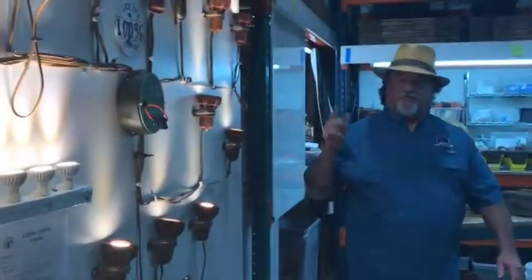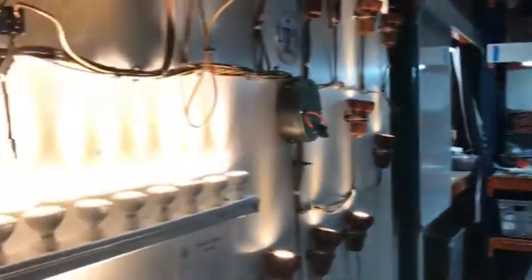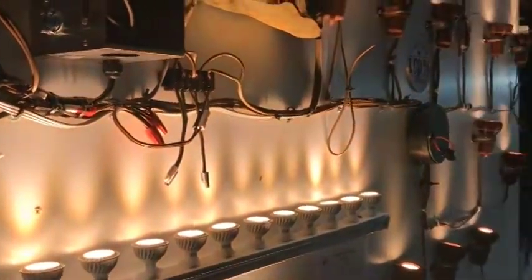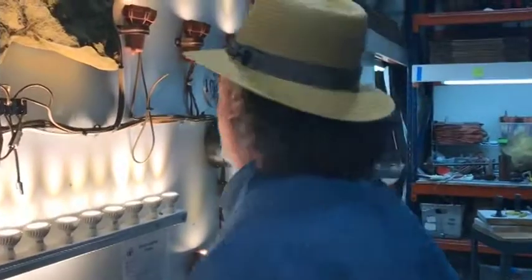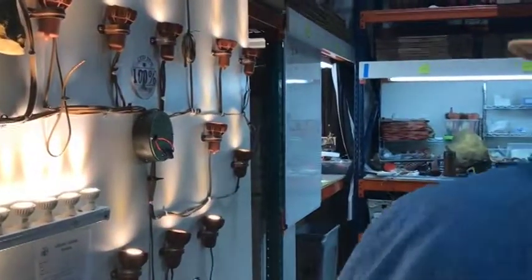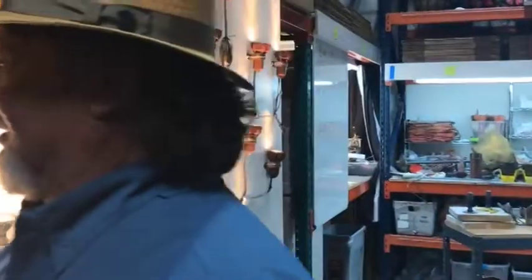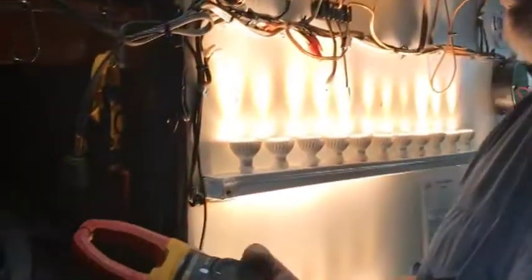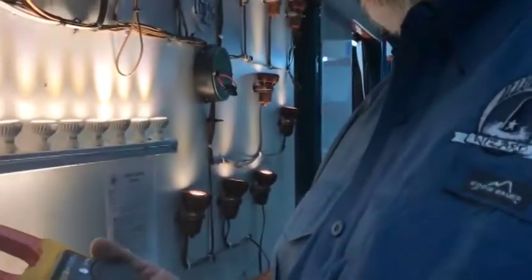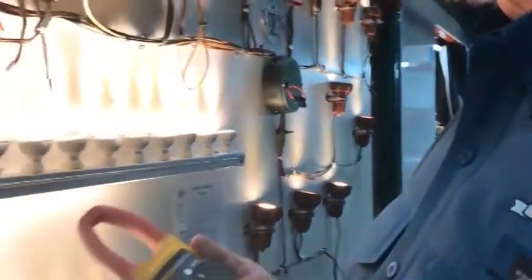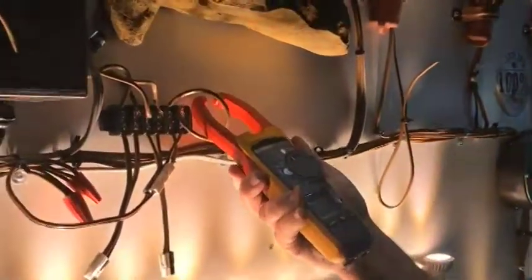I'm gonna hook it up to this guy. 22 and 28, which is 50 4-watt lamps. If you do the math, that's at least 200 without a power factor. All right, we want to take our amp probe, and we're gonna check some readings here. So first of all, I think I'll check the secondary.